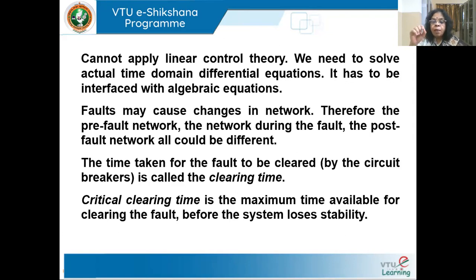Clear? So clearing time is the time taken to clear the fault. This will include the period from the fault initiation till the fault clearance, so that will take into account the relay operating time, the breaker operating time, and so on. Now, as I told you, if the fault lasts for a longer time, there is more chance that the system will become unstable.